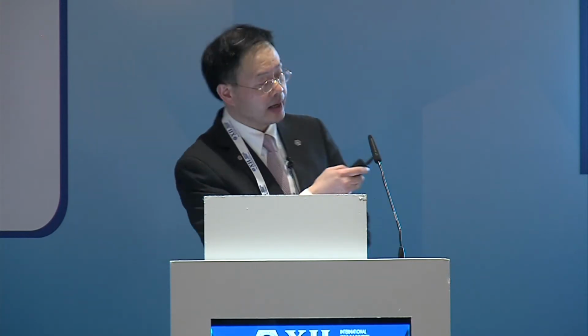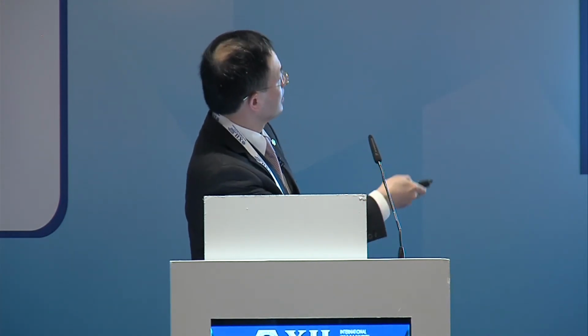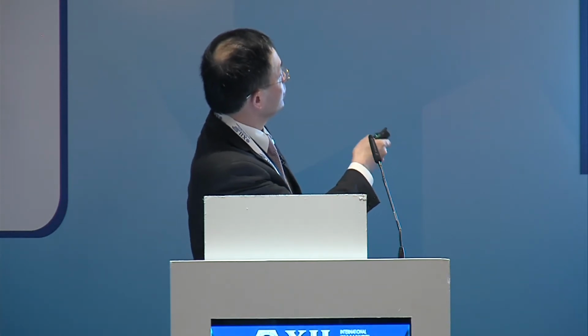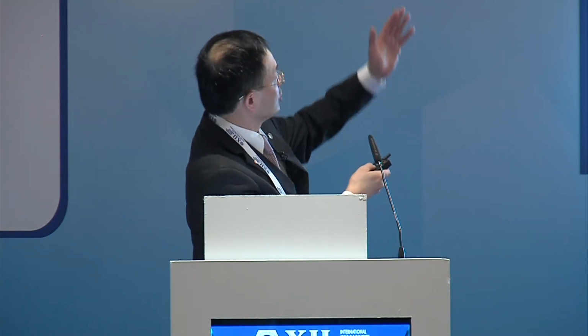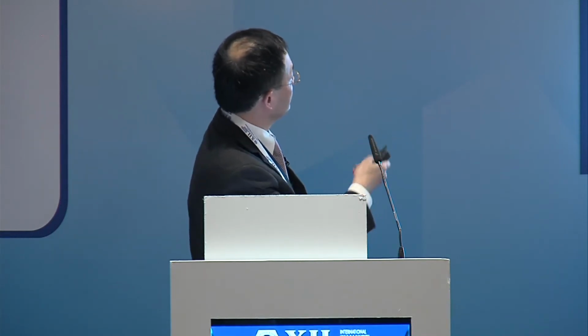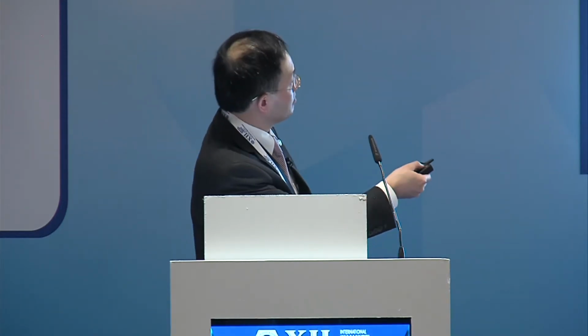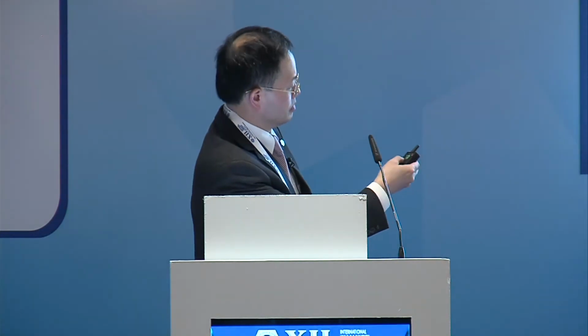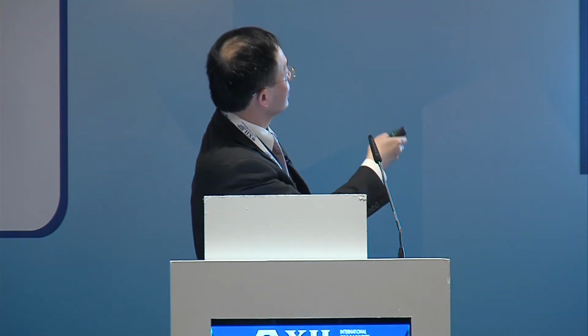There are two different types of concept in the US. One is where you see the HEPA filters above the patient bed. The other design style uses linear diffusers. You may put a HEPA filter inside the AHU level or the filter bank, then you discharge the clean air through these linear bars. Typically in the US this is more common, but in the old days you find lots of designs like that. The airflow arrangement is pressurized to push the air outside or to the restroom.